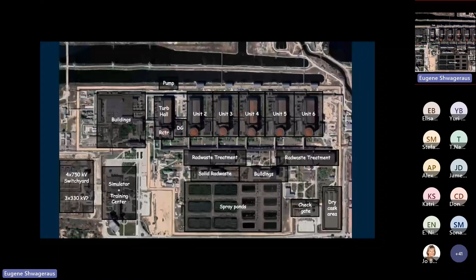The real limit is the temperature of the cooling pond, which if it reaches 30 degrees or more, impacts the vacuum of the condenser and reduces efficiency of the power plant. So that's the real limit. Keeping the cooling pond temperature below 30 degrees is done by managing how much heat you dump into the cooling towers versus the cooling pond.